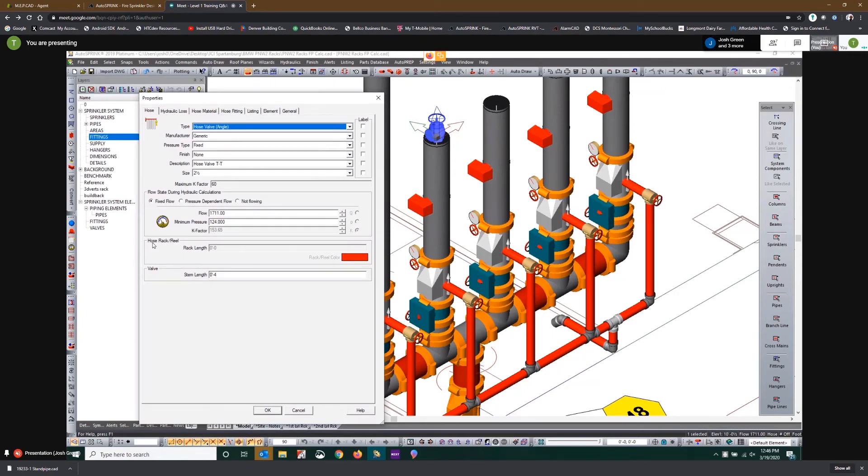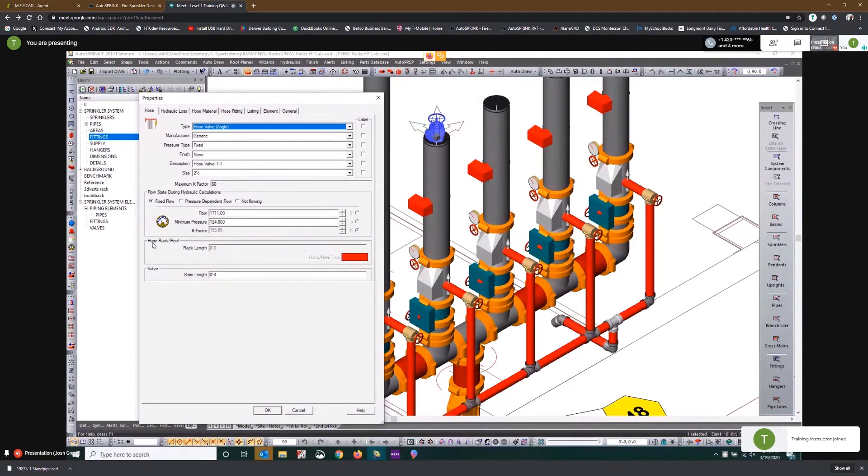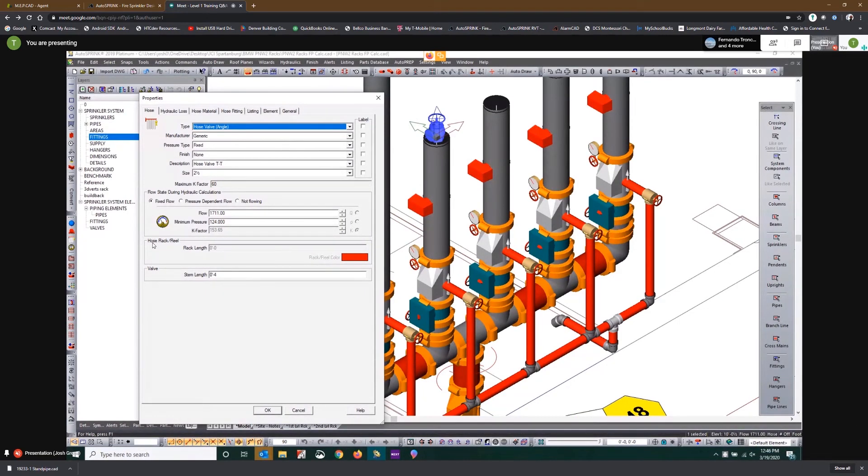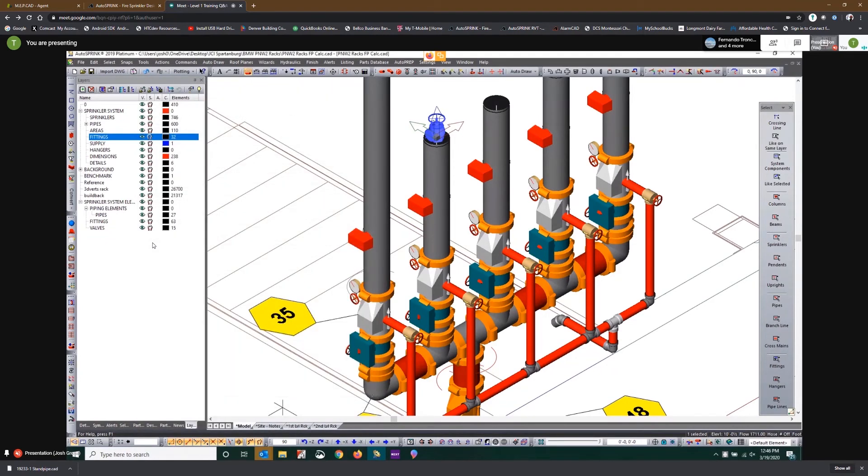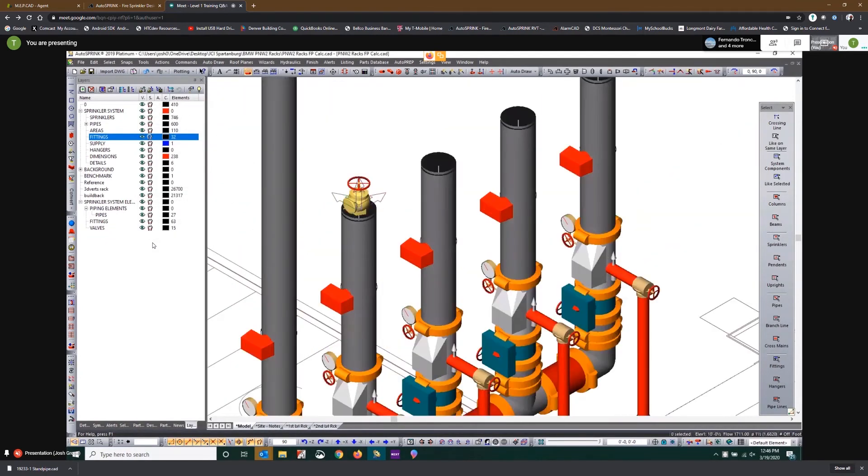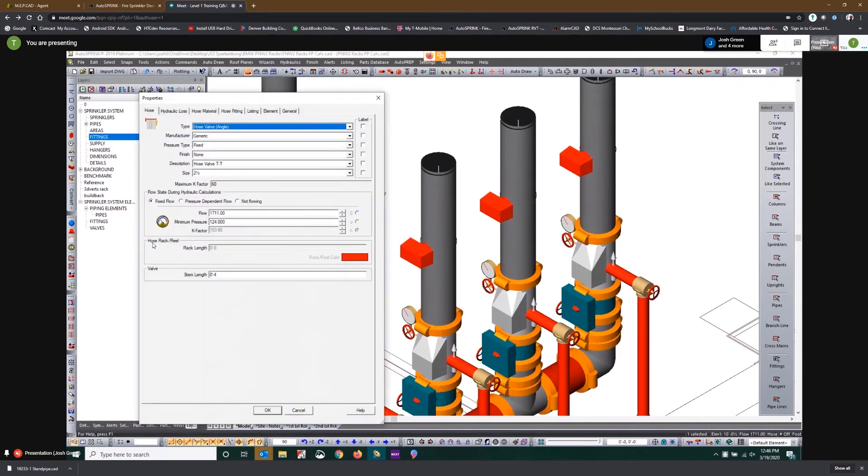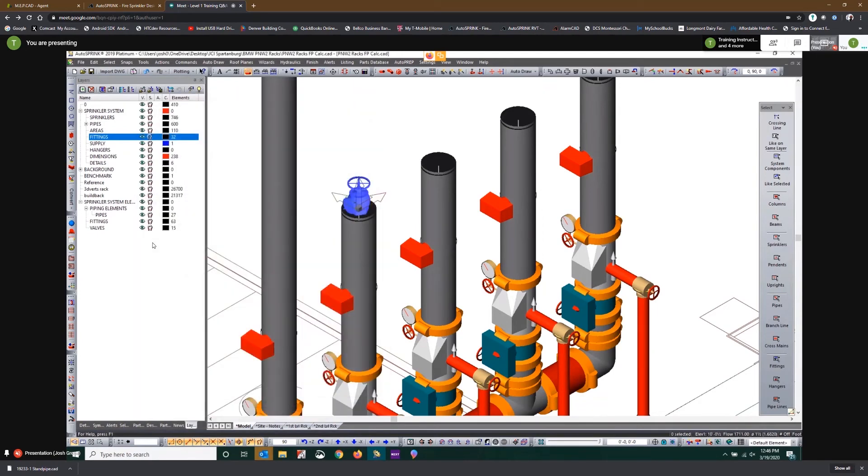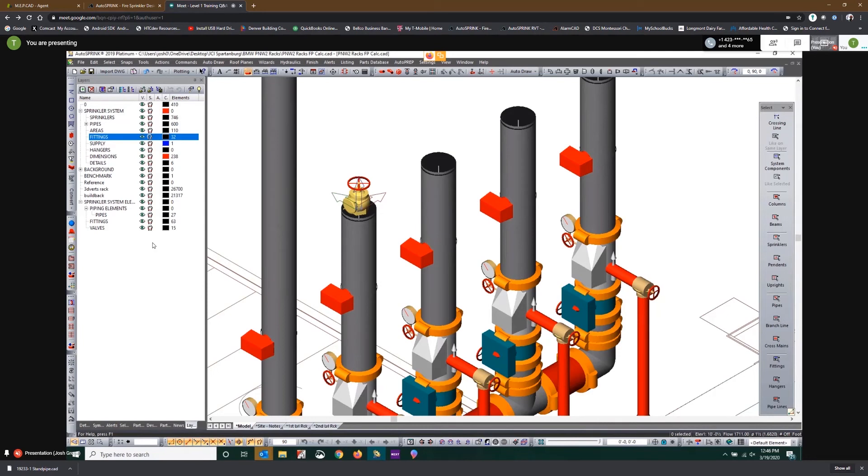When we switch that to pressure dependent flow, the program will maintain the k-factor that we establish based on the minimum pressure and flow and then it will adjust the flow rate based on the pressure that's required at that point in the system. Can I name that? Well unfortunately no. What happens here is that we're mimicking an existing system demand to balance with this new rack system, and the only way to really effectively mimic that system without designing it and placing a remote area is to utilize a hose valve.